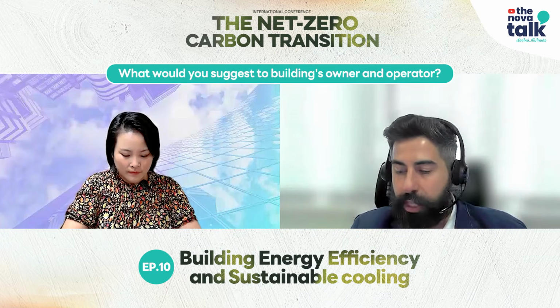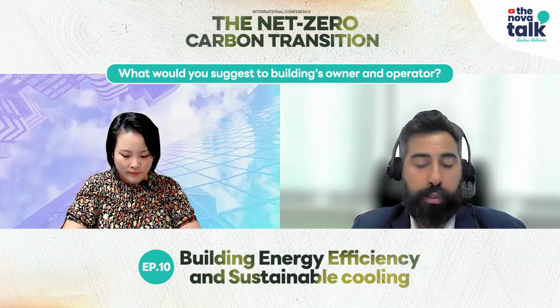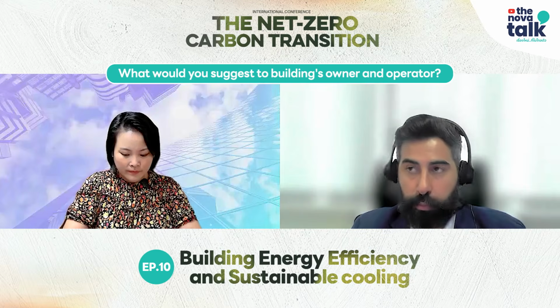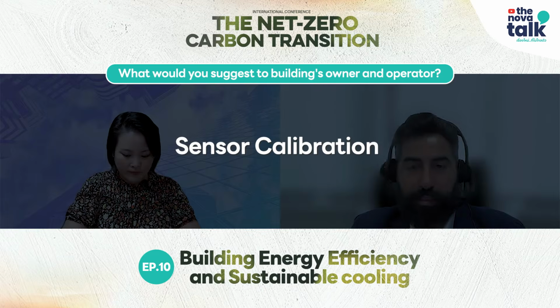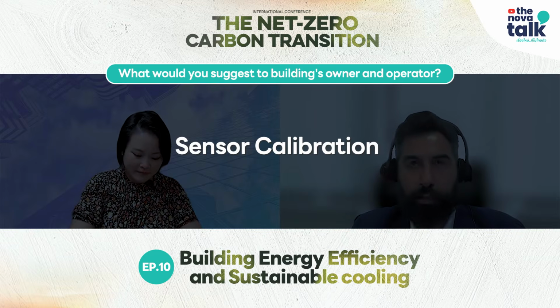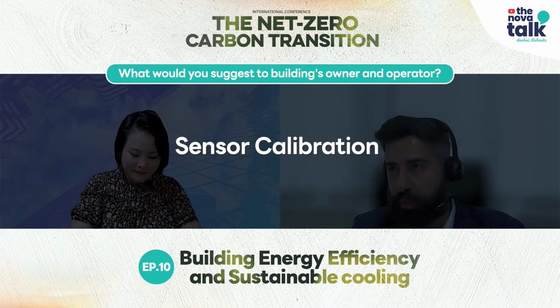The other issue I find in buildings is maybe you would have the best building automation system or building management system, but the sensors are never calibrated. So you wait for 1-2 years, you go into the BMS and find the sensors are just giving wrong numbers and wrong readings.